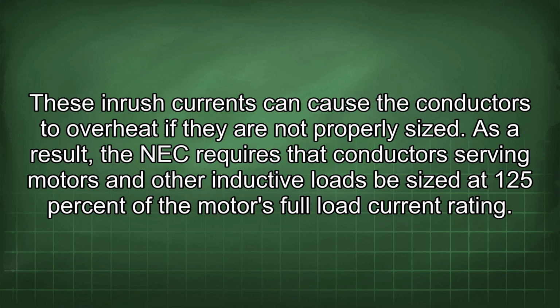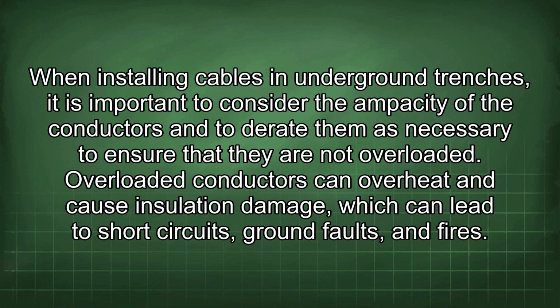These inrush currents can cause the conductors to overheat if they are not properly sized. As a result, the NEC requires that conductors serving motors and other inductive loads be sized at 125% of the motor's full load current rating. When installing cables in underground trenches, it is important to consider the ampacity of the conductors and to derate them as necessary to ensure that they are not overloaded. The overloaded conductors can overheat and cause insulation damage, which can lead to short circuits, ground faults, and fires.